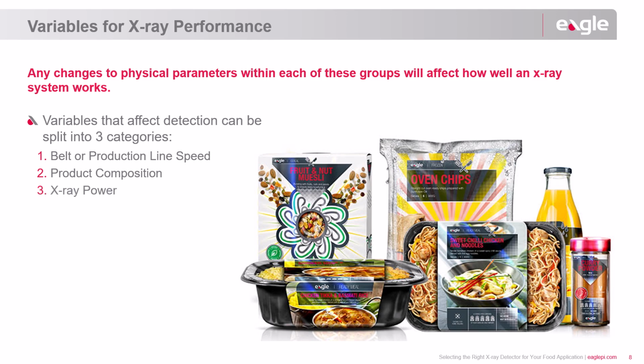X-ray energy levels involve 2 important components: kilovolts. This is the power of the X-ray. Higher kV means the X-ray can penetrate deeper into dense products to uncover hidden contaminants. Milliamperes measure the amount of usable energy that passes through the product for analysis. Higher mA means better quality data and more reliable detection.